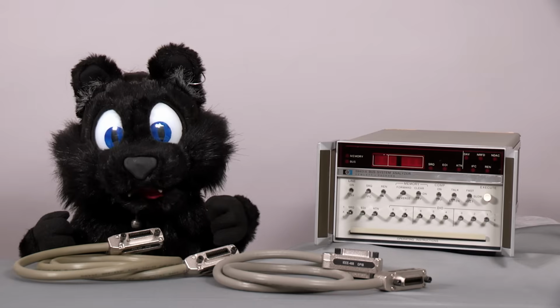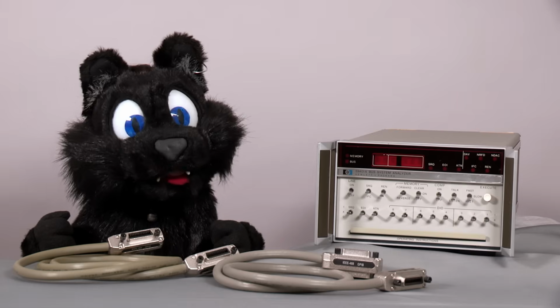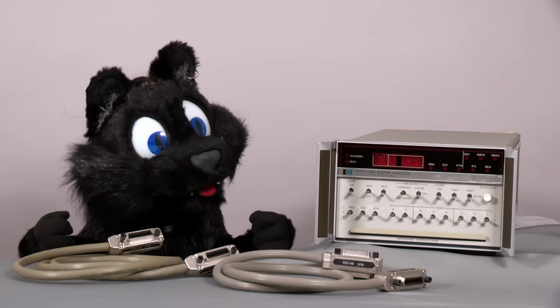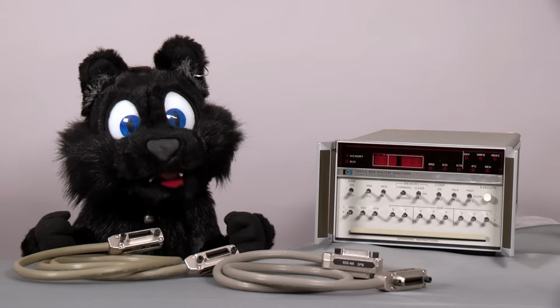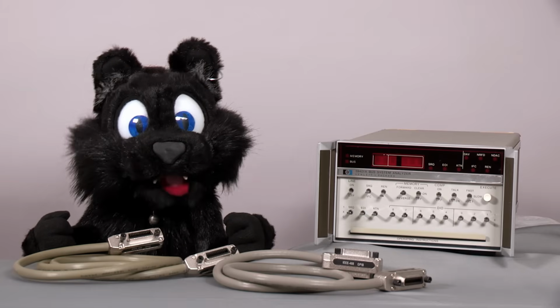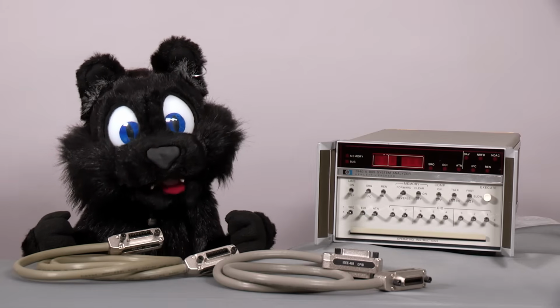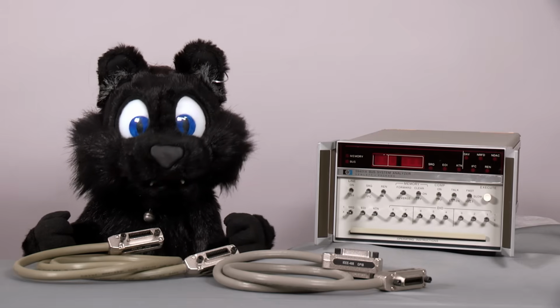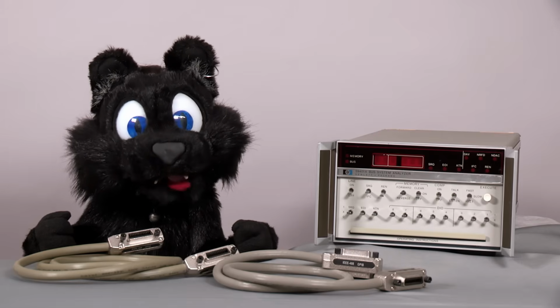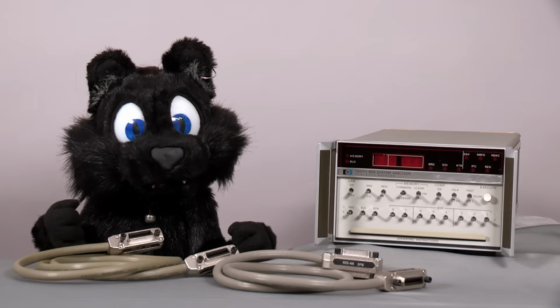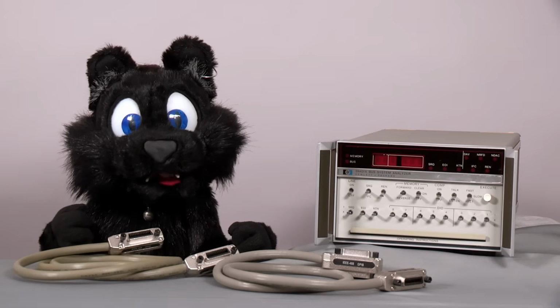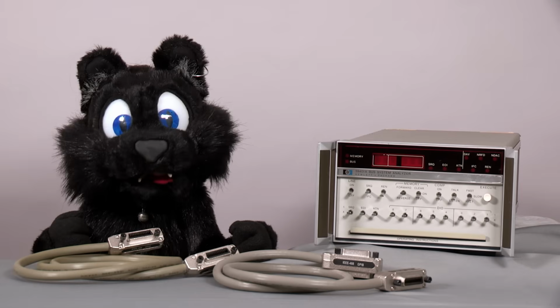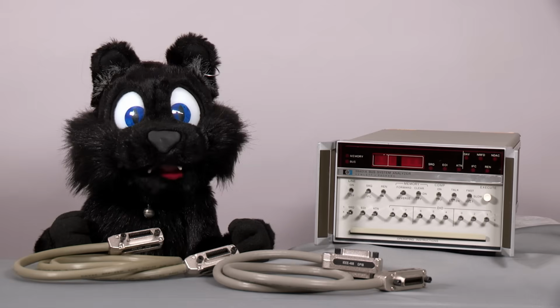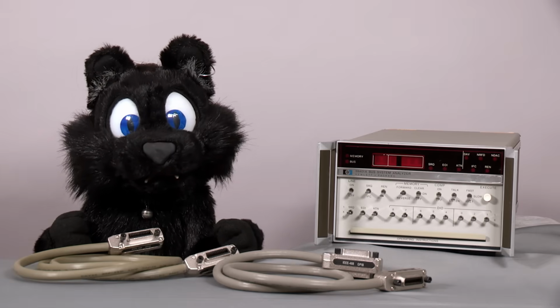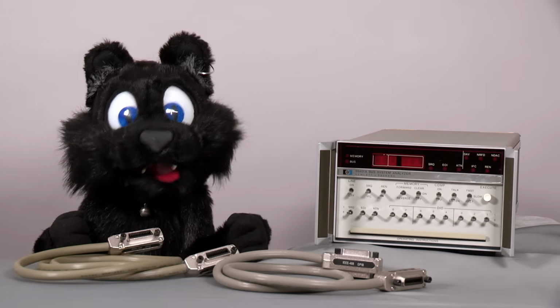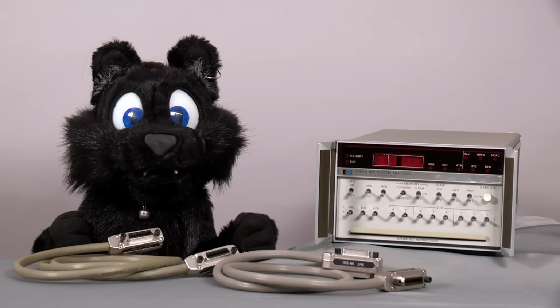Following the tube-based project from last episode, I have something from the early digital section again this time. This device, an HP 59401A, is a bus analyzer for the HPIB, the HP Instrument Bus, or more generally known as GPIB, General Purpose Instrument Bus, which is an IEEE standard, IEEE 488 if you like numbers. I'll be using the more modern GPIB name, but HPIB is the groundwork for that standard, so essentially they are the same, pretty much like SSL and TLS for the computer folk out there.